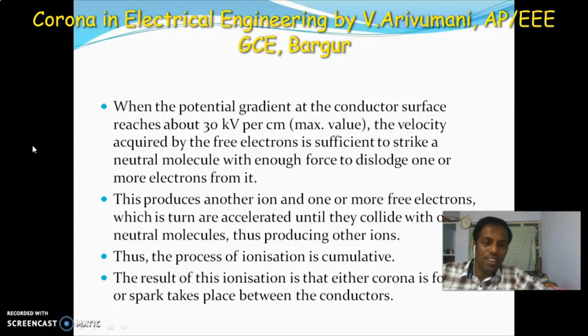Okay, what are the various factors affecting the corona? First one, atmosphere. The number of ions depends upon the atmospheric conditions. As corona is formed due to ionization, in stormy weather the number of ions is more than normal, and as such, corona occurs at much less voltage as compared with fair weather. In rainy and cloudy seasons, the ions are more compared to dry atmospheric conditions, so the corona will occur easily at less voltage. For example, in dry condition, 30 kV per centimeter is the limit. In rainy season, the limit reduces to around 20 or 25 kV per centimeter.